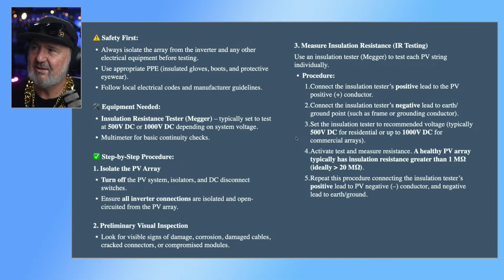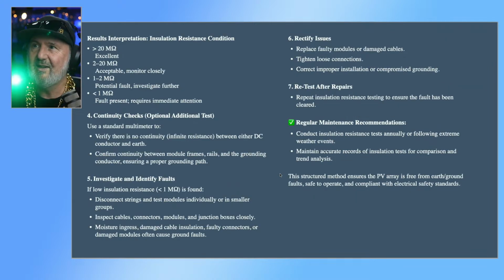Set the insulation tester to your 500 or 1,000 volt range and check what the impedance is. So resistance, because it is DC. The resistance should be greater than a megohm, ideally 20 megohms. There is actually some guidance in 5033, depending on the size of the array, the number of kilowatts, on what that value should be. So check that. So there you go. That's step one, or step three, I should say.